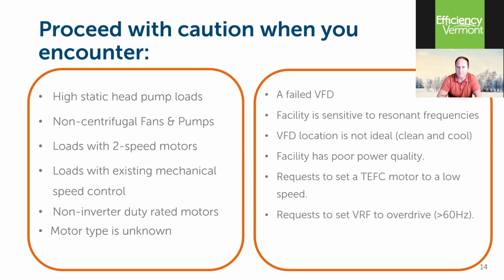This isn't a deal breaker. I have customers who run dust collector fans over 60 hertz for clean out mode. A drive will allow you to do that. That's the only way you can do it, really. It's only for a short duration of time to clean out the ducts. The rest of the time, the system modulates and does what a drive is supposed to do, which is deliver energy savings by way of shaft speed modulation.